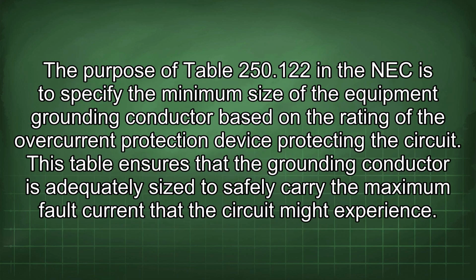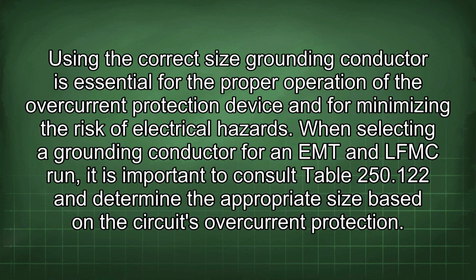The purpose of Table 250.122 in the NEC is to specify the minimum size of the equipment grounding conductor based on the rating of the overcurrent protection device protecting the circuit. This table ensures that the grounding conductor is adequately sized to safely carry the maximum fault current that the circuit might experience. Using the correct size grounding conductor is essential for the proper operation of the overcurrent protection device and for minimizing the risk of electrical hazards.